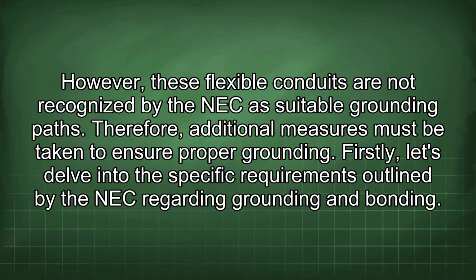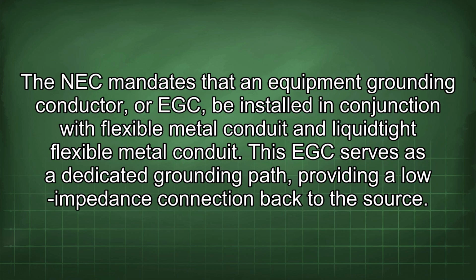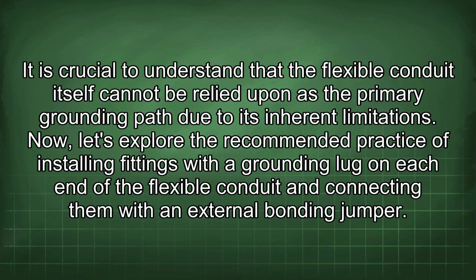Firstly, let's delve into the specific requirements outlined by the NEC regarding grounding and bonding. The NEC mandates that an equipment grounding conductor, or EGC, be installed in conjunction with flexible metal conduit and liquid-tight flexible metal conduit. This EGC serves as a dedicated grounding path, providing a low impedance connection back to the source. It is crucial to understand that the flexible conduit itself cannot be relied upon as the primary grounding path due to its inherent limitations. Now let's explore the recommended practice of installing fittings with a grounding lug on each end of the flexible conduit and connecting them with an external bonding jumper.